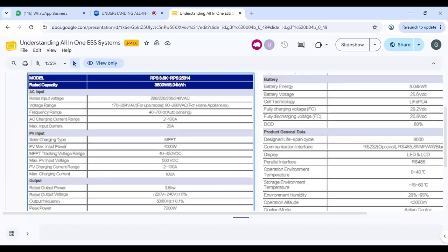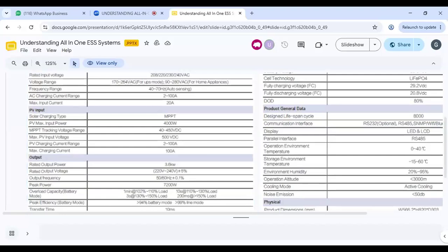For the PV charging current, the range is from 2 amps to 100 amps. And what they mean by that is the current that goes into the battery. Because anytime you see charging currents and you see the range very high like that, like 100 amps, 80 amps, it's talking about the current that's going into the battery. Then maximum charging current is 100. That's why the range was from 2 to 100 amps. You know, it's lithium ion. It varies based on demand and the communication between the battery and the inverter itself.